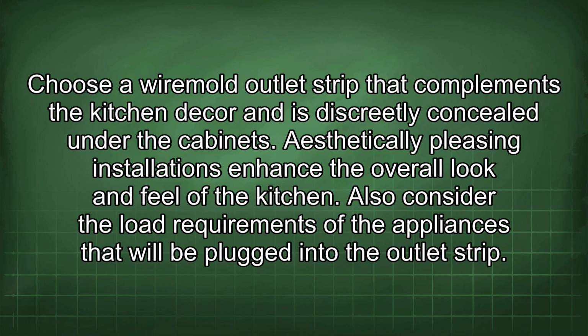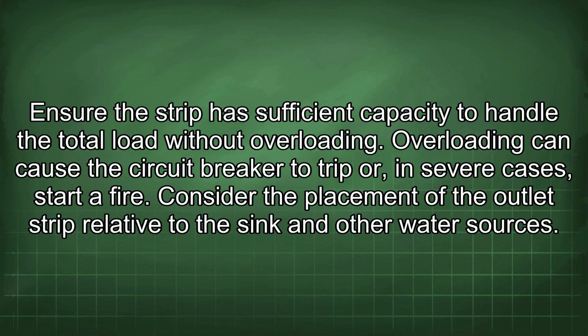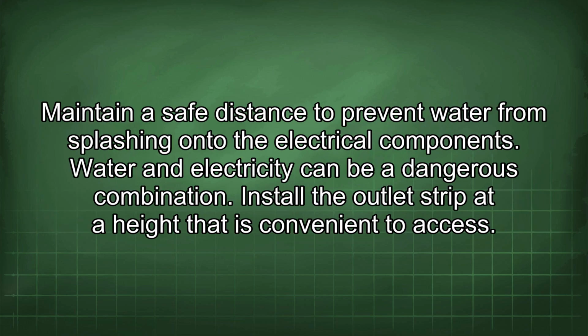Also consider the load requirements of the appliances that will be plugged into the outlet strip. Ensure the strip has sufficient capacity to handle the total load without overloading. Overloading can cause the circuit breaker to trip or, in severe cases, start a fire. Consider the placement of the outlet strip relative to the sink and other water sources. Maintain a safe distance to prevent water from splashing onto the electrical components. Water and electricity can be a dangerous combination.